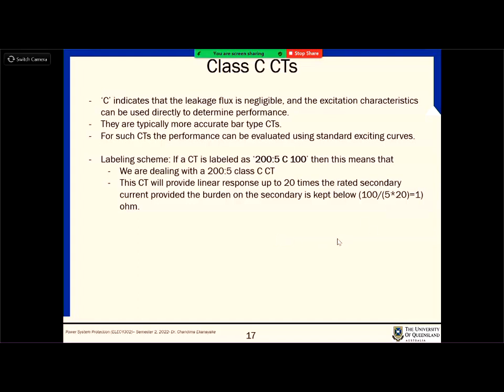Which means that if you keep a 1 ohm resistor across the secondary, let's say the whole impedance in the secondary is 1 ohm, then even at 20 times the fault current, like if the fault current is 20 times the full load current, the CT is working perfectly. That's why we use that 20 in the calculations. Okay?